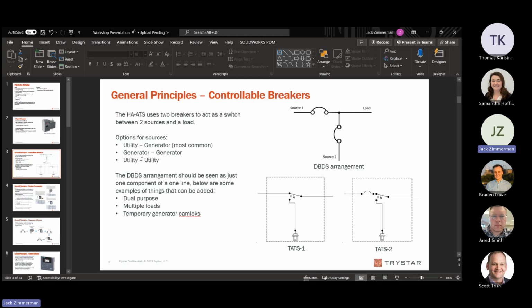So you absolutely can have different power sources. The unit we have out there does have different power sources. It's just fairly atypical to see renewables coming into an ATS, an automatic transfer switch. It would be a rare enough case where I didn't mention it, to just see renewables coming into one side and having a hard transfer over to them. A lot of renewables like to sit in line on the utility waveform.